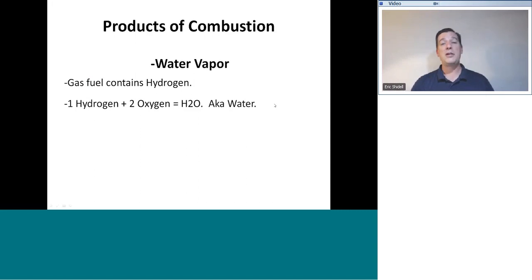Under conventional combustion, this water remains in vapor state. In the flame, we are literally combining hydrogen plus oxygen, creating water vapor in the flame. But it's water vapor. And the flame, of course, is a very high temperature, so that's way above the boiling point of water, so that water stays in vapor form. However, when that flue gas cools, that water vapor will turn into water droplets, and then it will start to run out of places.